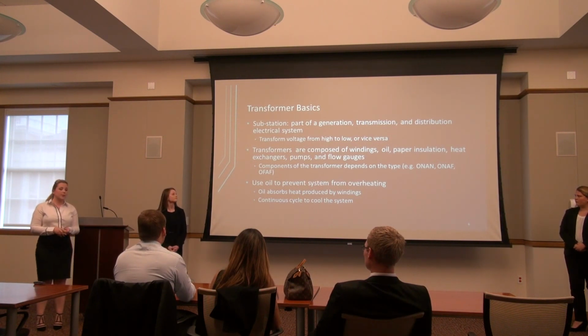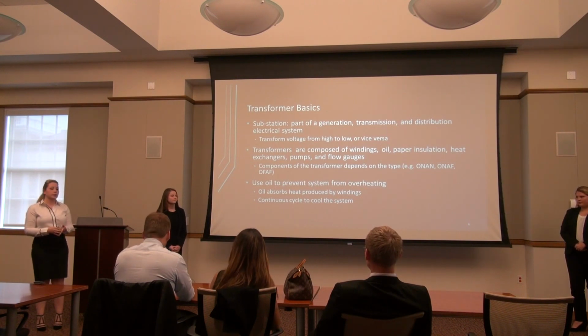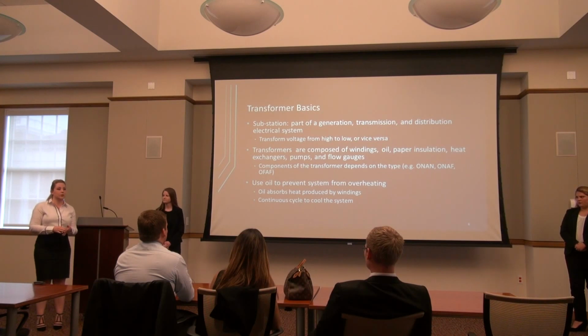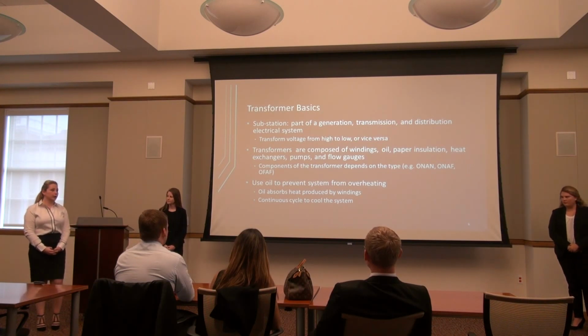Transformers have several different components, and these components vary depending on the type of transformer. The three main types are oil natural air natural, oil natural air forced, and oil forced air forced. The 20 transformers at Weatherford are all oil natural air forced, which means that the oil and the air circulate naturally, but there are also fans that perpetuate the circulation of the air.